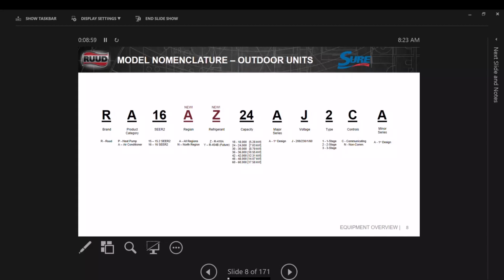This is your voltage. Pay close attention to that, because I've had probably 2 calls this year where we've put 3-phase equipment in where it was supposed to be single phase or vice versa. And of course, this is your stage type, 1, 2, 3, 4, your stages. Your controls, if it has a C, means communicating, pretty basic. N is non-communicating. And then we have another design series code there in the end. Just so you kind of understand what the nomenclature is telling you when you're looking at it. And all of our units in the spec sheets of that particular unit, whether it be a condenser or a furnace, an air handler, or a coil, we have one of these charts in each one of them so you can tell what each one of those letters means.